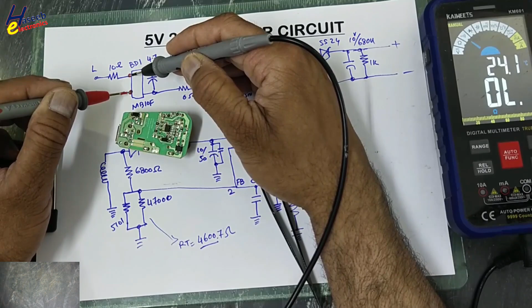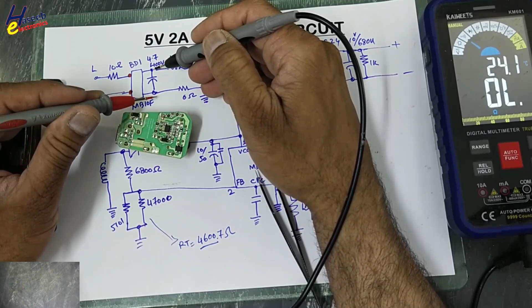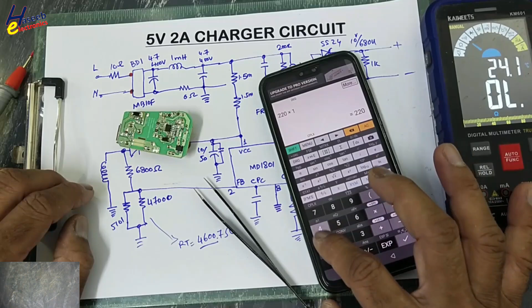If we apply power, we will receive 220 volt AC here. We measure the 220 volt input and multiply by 1.414 to convert it into peak voltage. That voltage value must be present at these capacitors. Suppose I have 220 volts, multiply by 1.414, 311 volts must be present at these capacitors. If we have 311 volts, that's great - that means this capacitor is in good health.